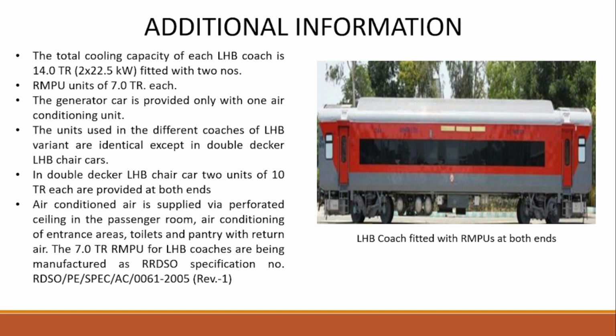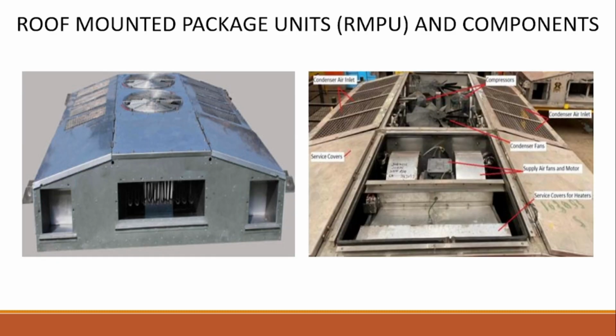The generator car that is used in the end-on generation process is provided with only one air conditioning unit. In the double-decker LHB chair car, two units of 10 tonnage each are provided at both ends. Air-conditioned air is supplied via a perforated ceiling in the passenger room, and air conditioning of entrance areas, toilets, and pantry is done with return air. So this is how an RMPU looks. There are several components in an RMPU. Let's take a look.